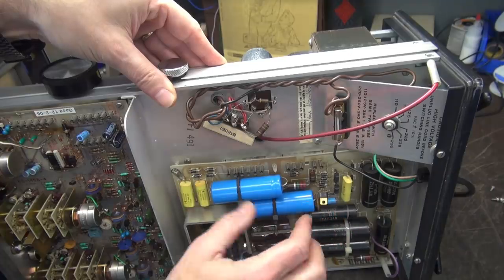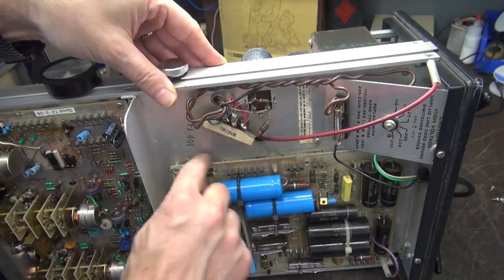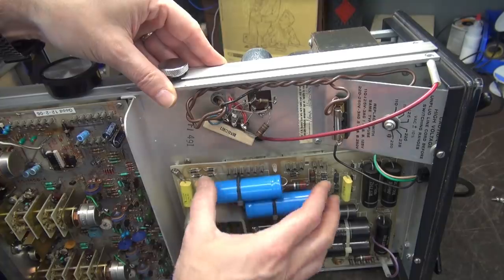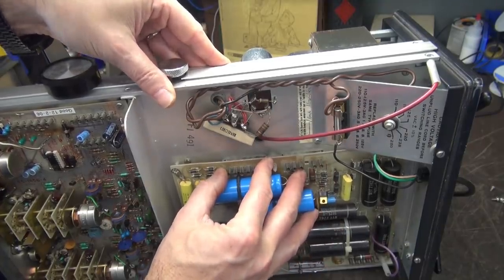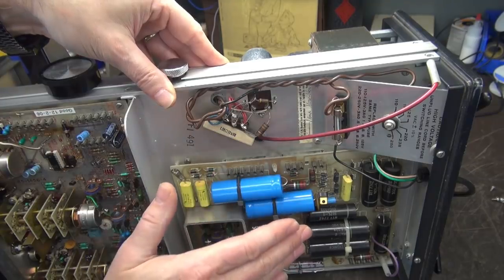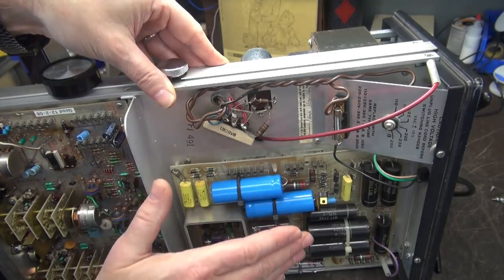So what happens is the board bows here in the center and these connections remain loose. They will not lock in and you'll have poor connections which will cause all kinds of issues with the scope.